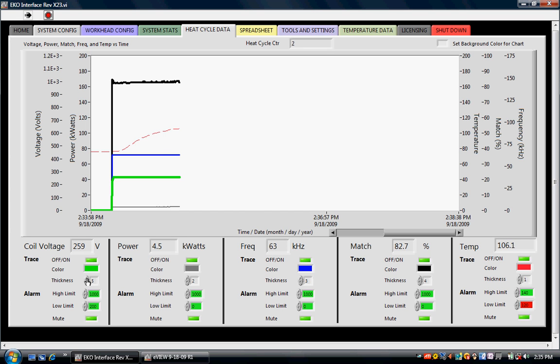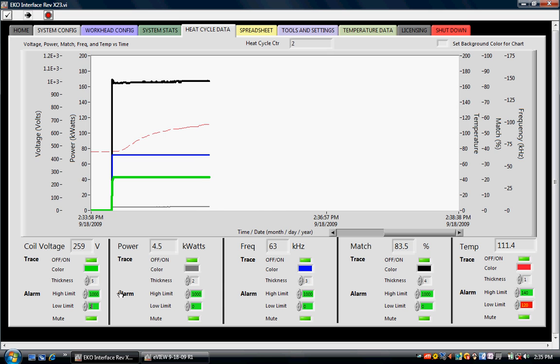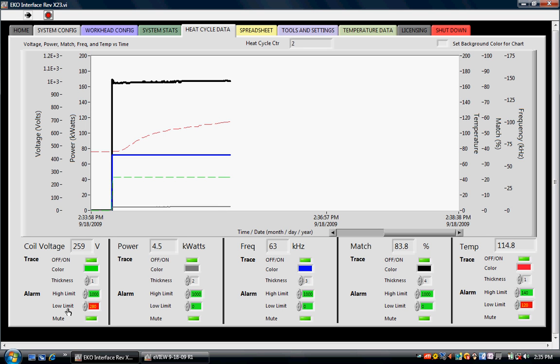Each induction heating parameter has a high limit and a low limit. Right now our coil voltage is 259 volts, our high limit is 1000 volts, our low limit is 200 volts. If we change our low limit to 280 volts, then we should see an alarm condition, and we do. During an alarm condition, the parameter that caused the condition turns red and flashes so we know the condition is caused by a low limit alarm on coil voltage. The coil voltage trace becomes a dashed line and there is an audible alarm inside the PC. Right now the mute button is on so we're not hearing it. If we take that mute button off, then we hear an audible alarm.